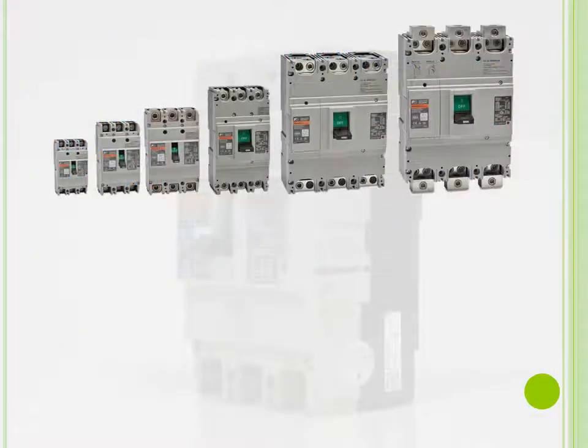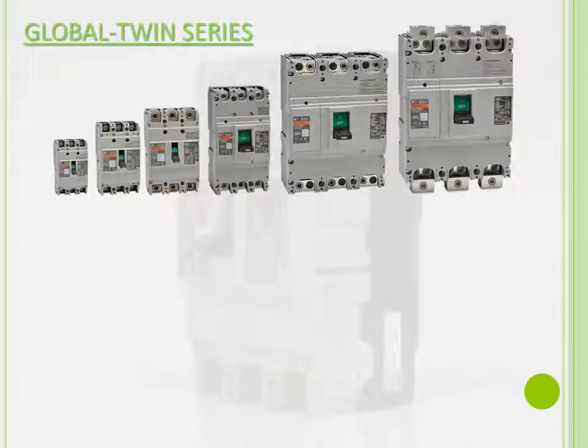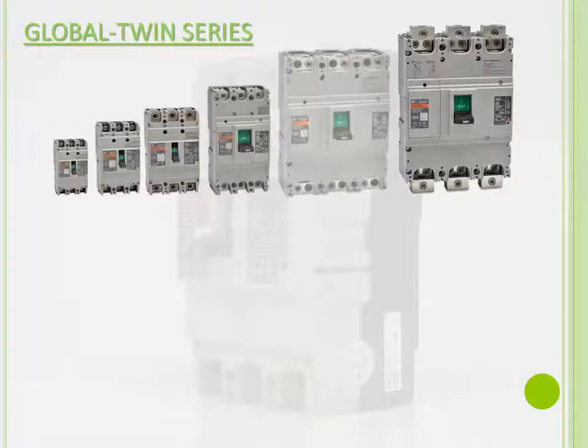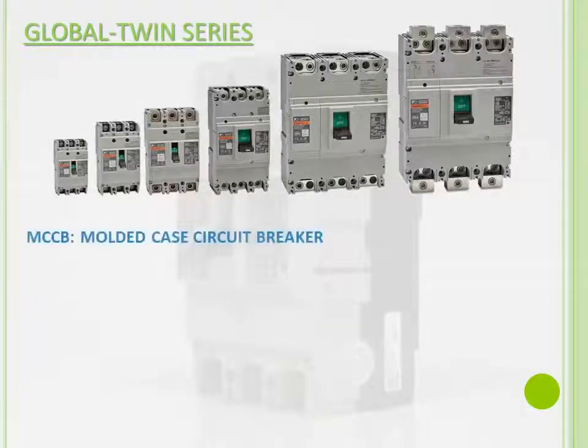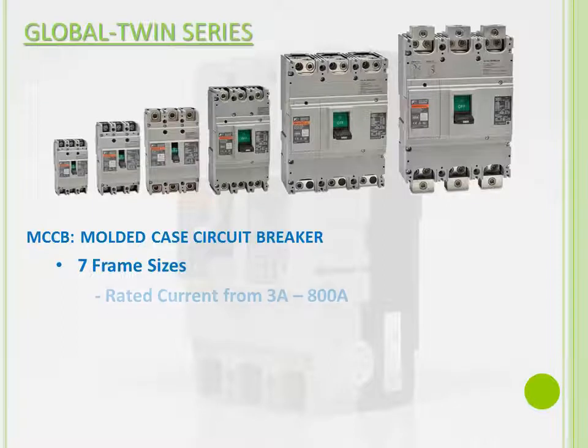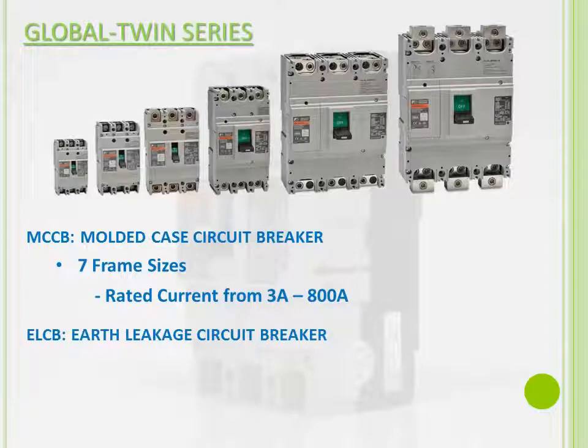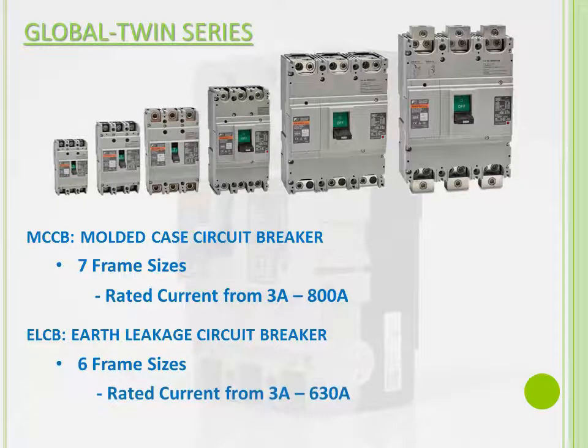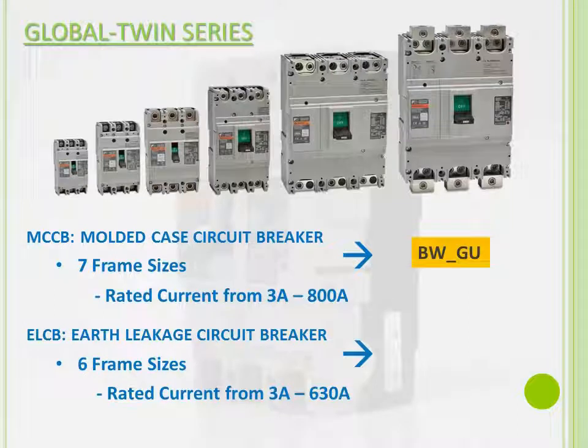Fuji Electric's current lineup of circuit breakers is the Global Twin series, or G-Twin for short. The MCCBs and ELCBs are identical in physical body and mounting pitch dimensions, hence the name Global Twin. The MCCBs have 7 frame sizes ranging from 50 amp frames to 800 amp frames, with rated currents starting from 3 amps up to 800 amps. The ELCBs, on the other hand, have 6 frame sizes ranging from 50 amp frames to 630 amp frames, with rated current from 3 amps to 630 amps. The MCCB is recognizable by the BW at the start of its part number, while the ELCB is recognizable by the EW at the start of its part number.